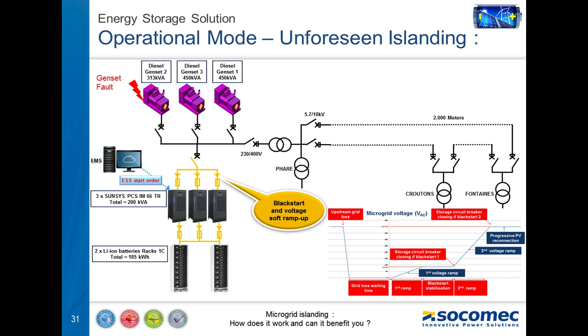of the load. In fact, in our system, we have two black start modes. The first one is dedicated to standard load, where there is no criticality concerning inrush current. And the second one is for motor load, or either low voltage or medium voltage transformer, which can create this kind of situation of inrush current. For the first mode, for standard load, the circuit breaker of the energy storage system is closed only when the voltage reaches the nominal voltage.